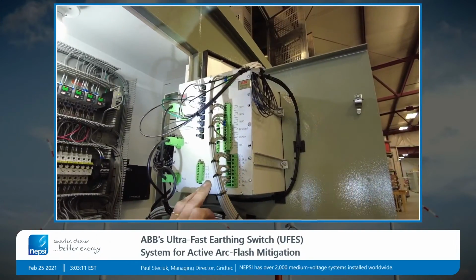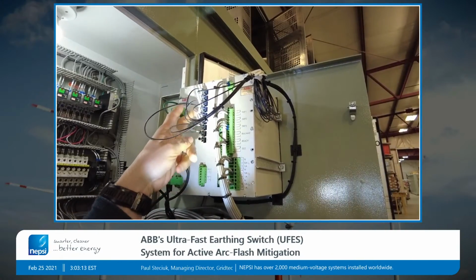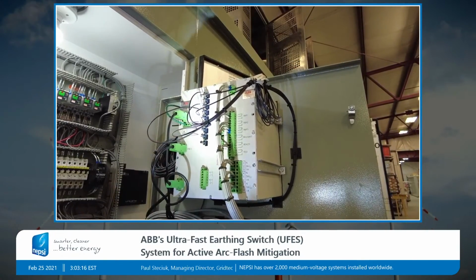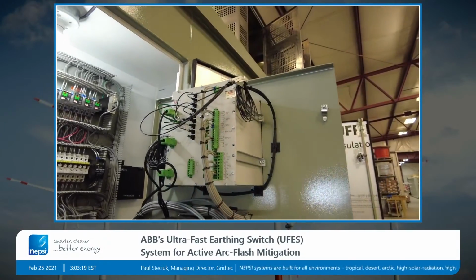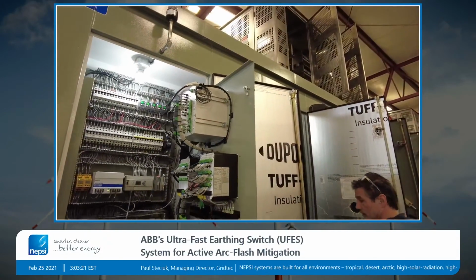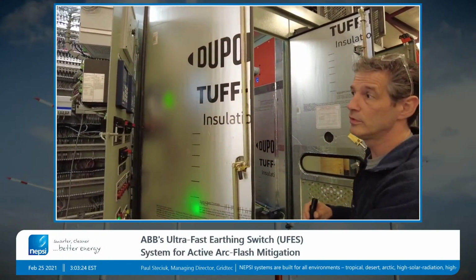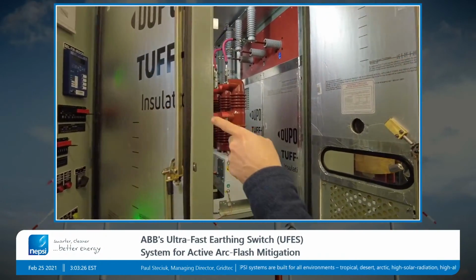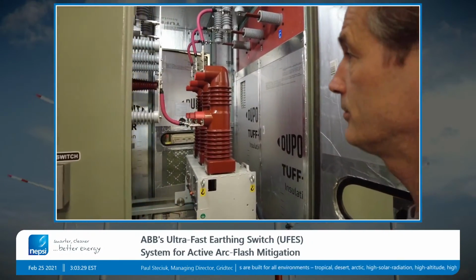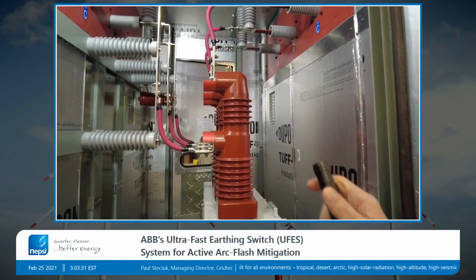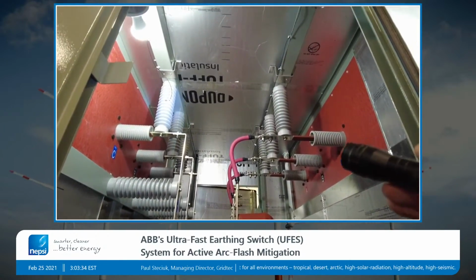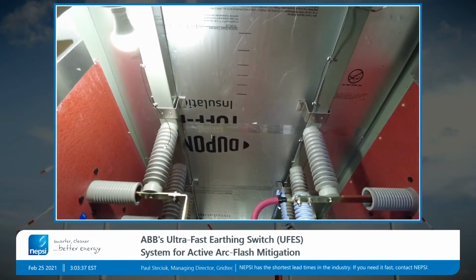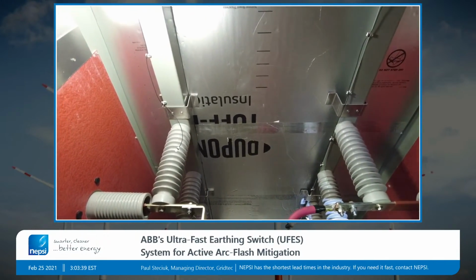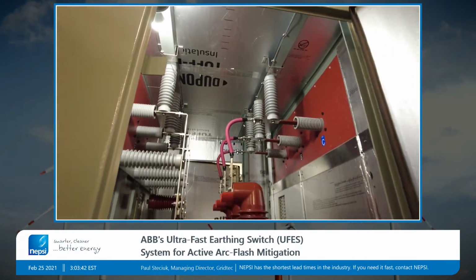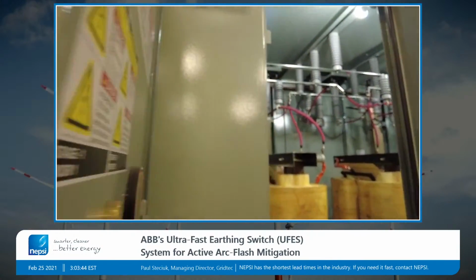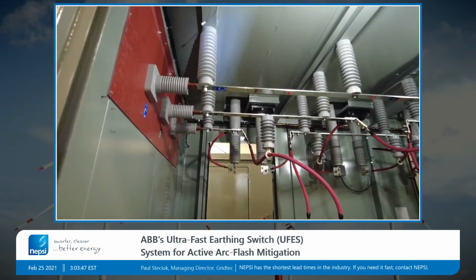So with this, we have optical sensors. For this project, we have a total of 8 optical sensors out of 9 being used. These optical sensors are located in the various compartments. We have 2 sensors located in the incoming isolation compartment, the source compartment. We have 2 located in the breaker compartment, you can see one right there, and another one over here. And then we have 4 located in the main reactor and capacitor compartment.